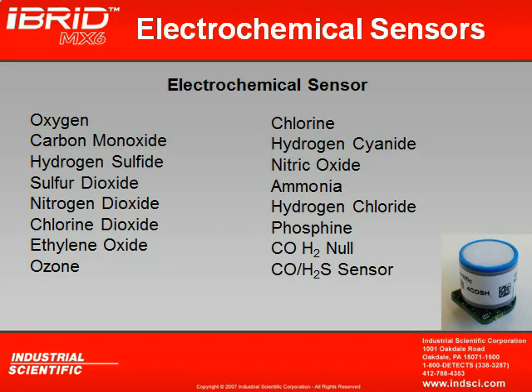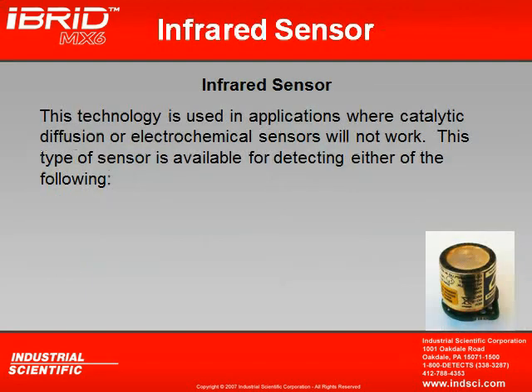Let's go ahead and talk about infrared sensors a little bit. Infrared sensors are completely different from your electrochemical counterparts. This technology is used in applications where catalytic diffusion or electrochemical sensors will not work. This type of sensor is available for detection of either of the following. We use this for detection of CO2, carbon dioxide, and we also use it for detection of methane, up to 100% by volume.